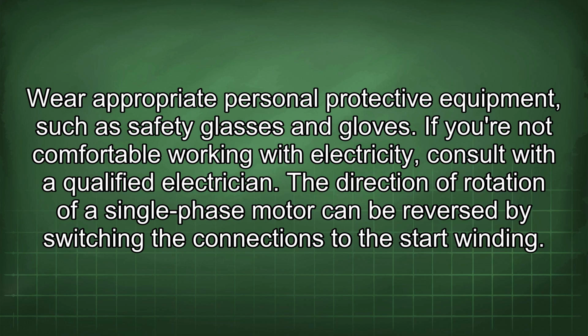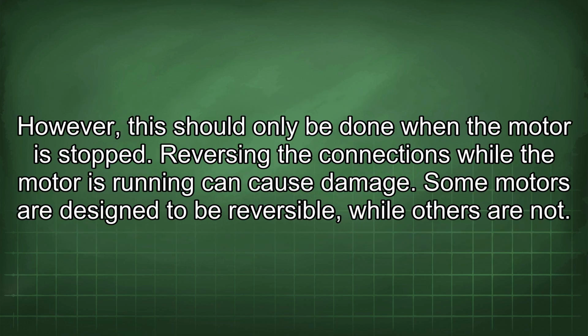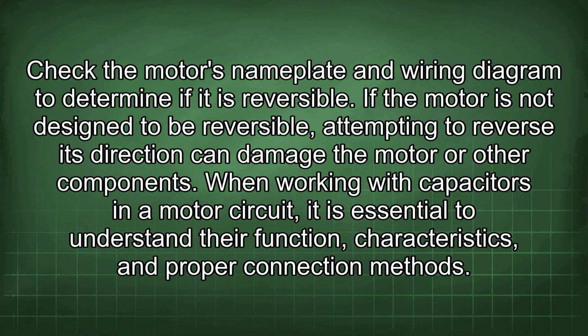The direction of rotation of a single-phase motor can be reversed by switching the connections to the start winding. However, this should only be done when the motor is stopped. Reversing the connections while the motor is running can cause damage. Some motors are designed to be reversible, while others are not. Check the motor's nameplate and wiring diagram to determine if it is reversible.